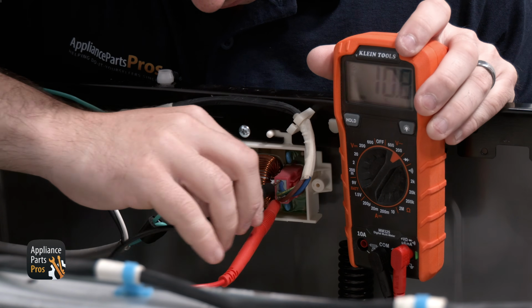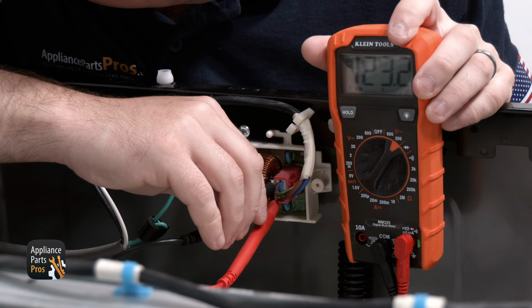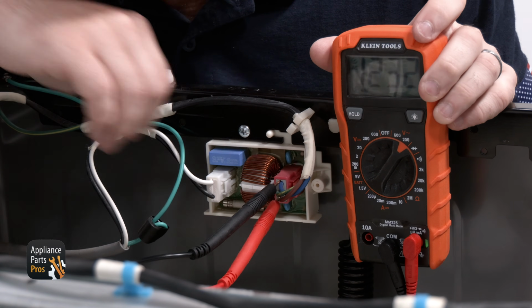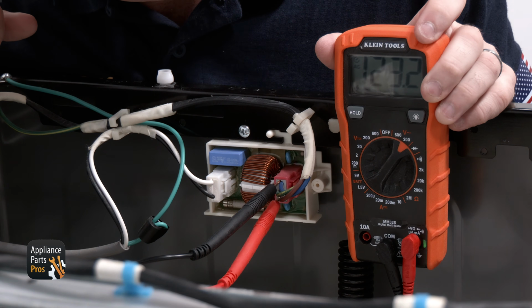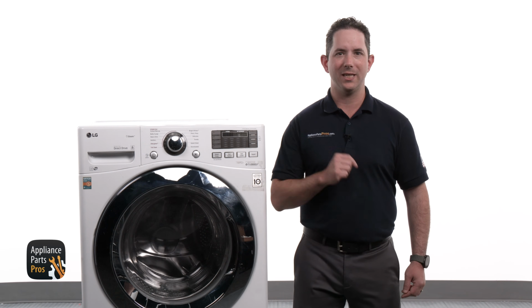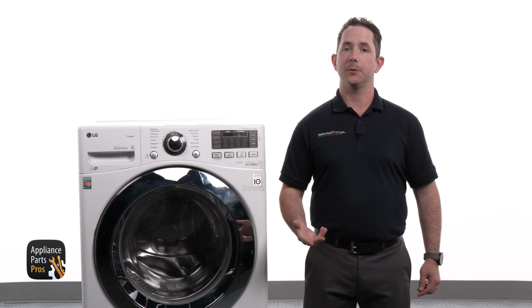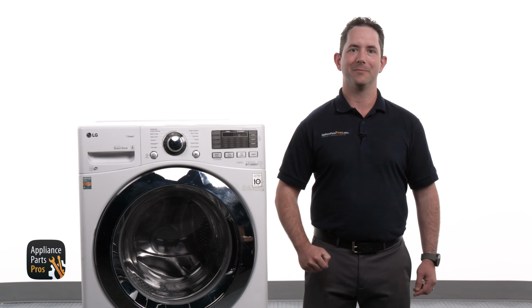If there is 120 volts present, we will do the same for the red connector. If there's not 120 volts AC present at the red connector, the noise filter has failed and would need to be replaced. If voltage is present, we can continue troubleshooting.